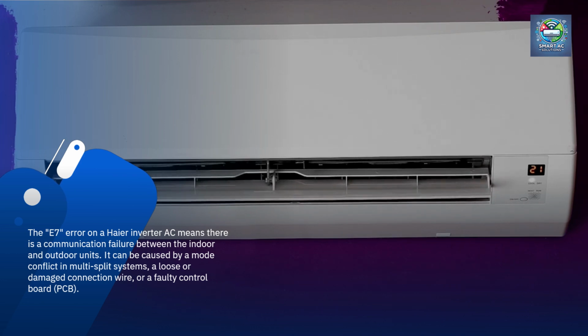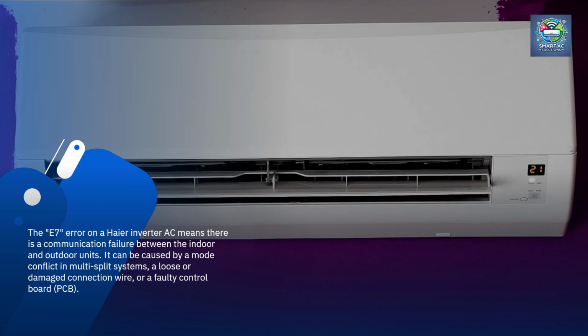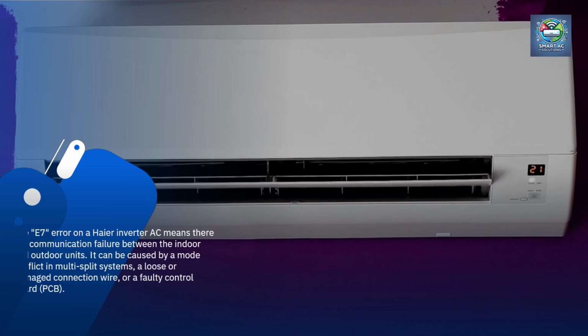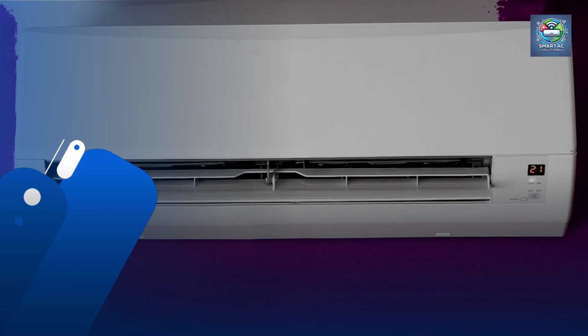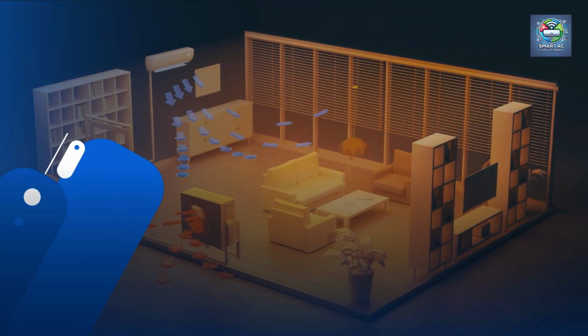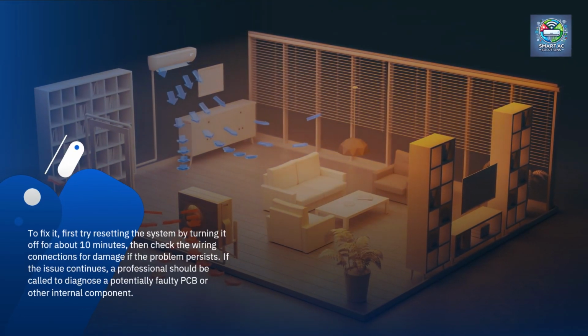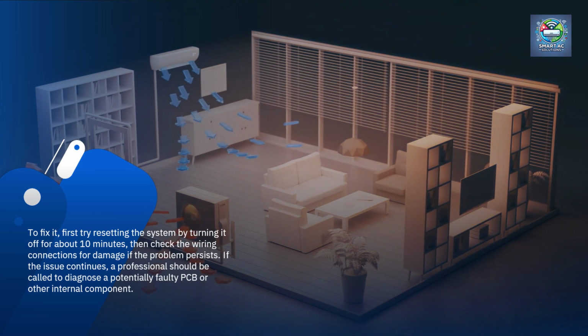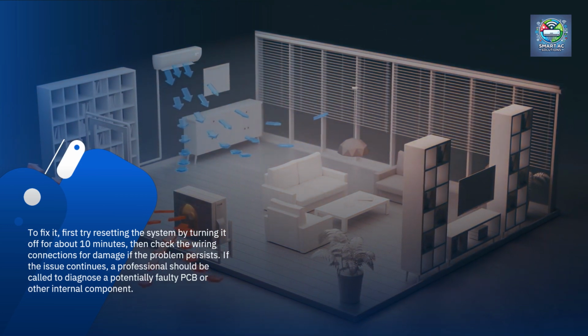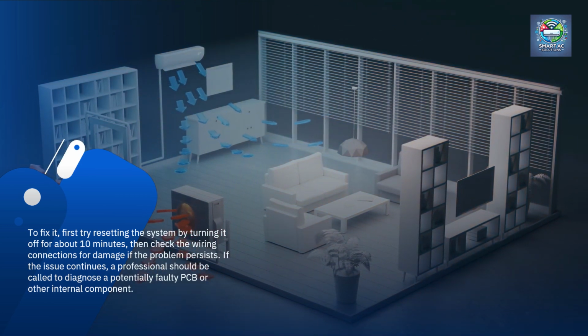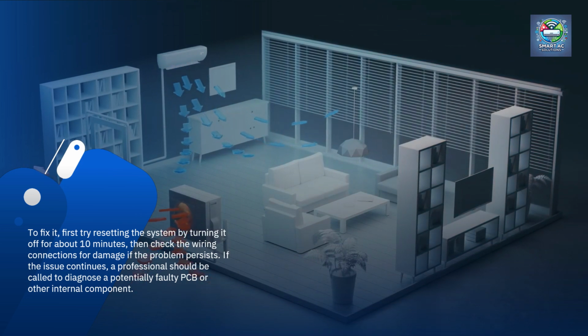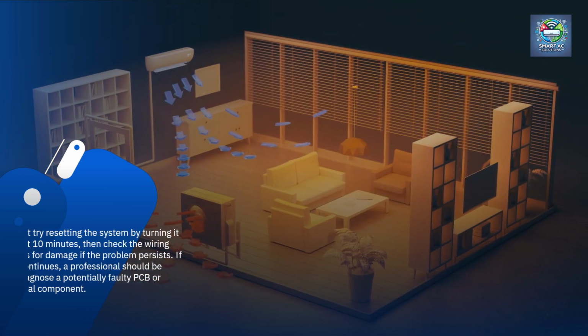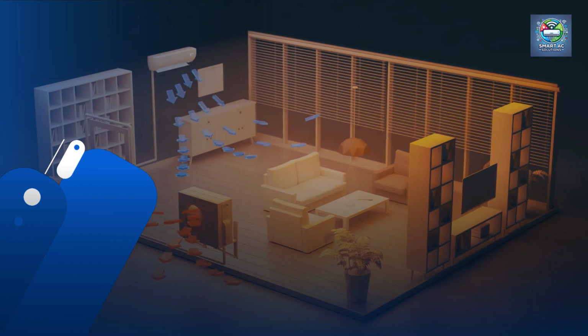It can be caused by a mode conflict in multi-split systems, a loose or damaged connection wire, or a faulty control board, PCB. To fix it, first try resetting the system by turning it off for about 10 minutes, then check the wiring connections for damage if the problem persists. If the issue continues, a professional should be called to diagnose a potentially faulty PCB or other internal component.